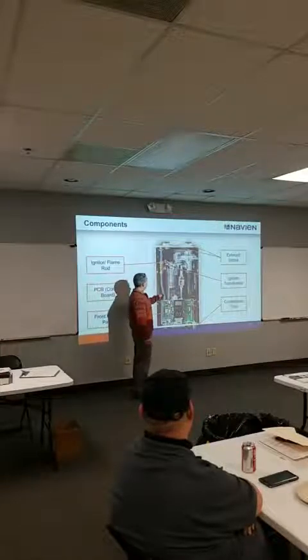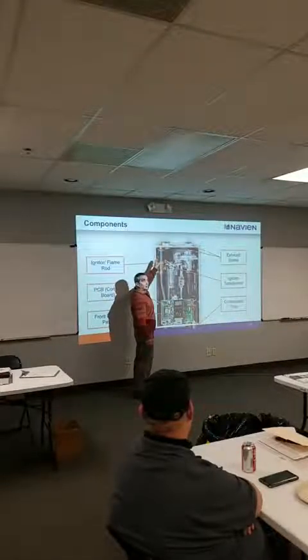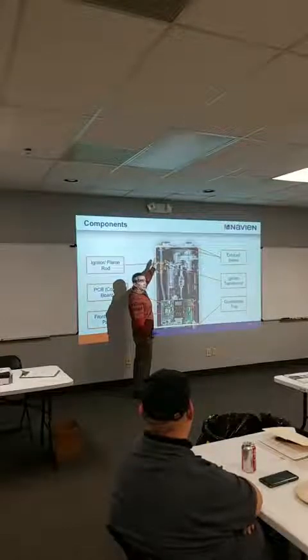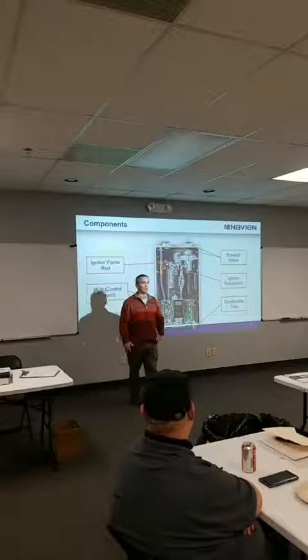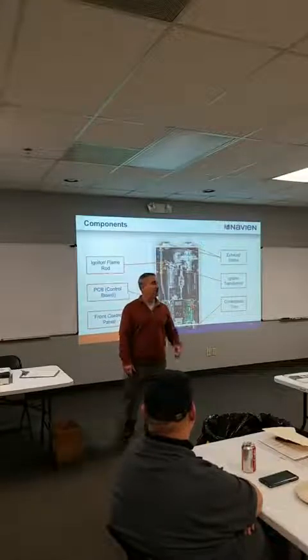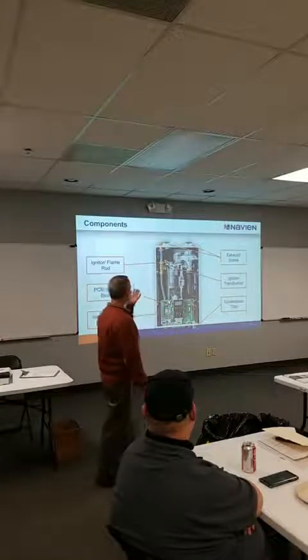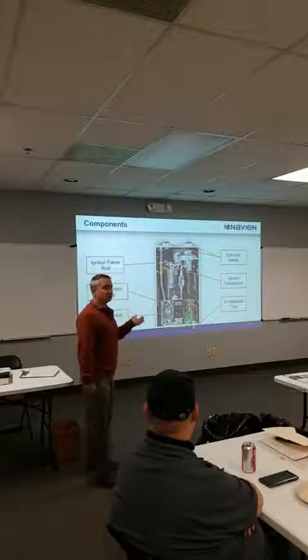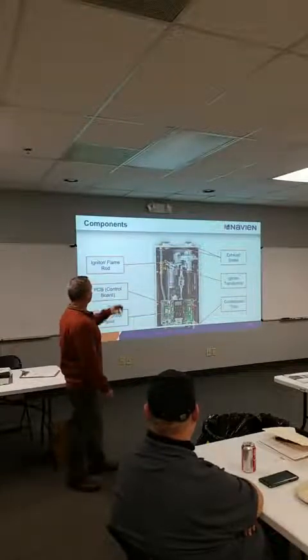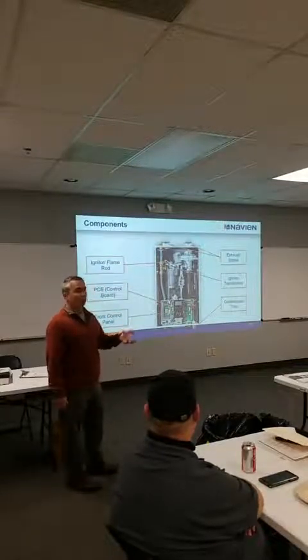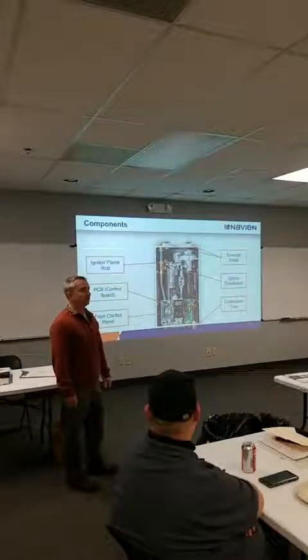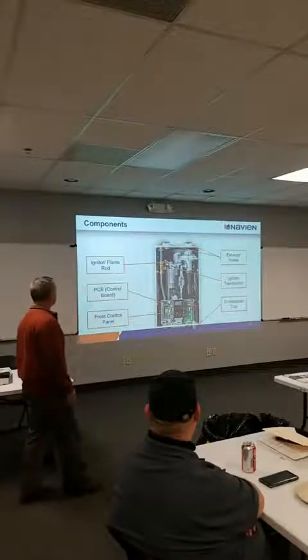This unit has piping that goes to the top. This is just for an air eliminator that we supply in the box, or you can tee off a relief valve there as well if you want, on top of the unit. That's to help get all the air out of the heat exchanger when you're doing your fill. You can actually just leave that open as you're filling the boiler, and when water starts coming out the top, you know that fire tube heat exchanger is full.